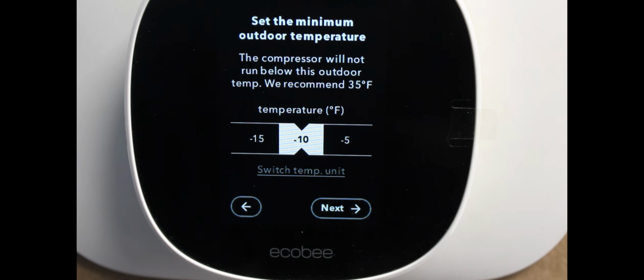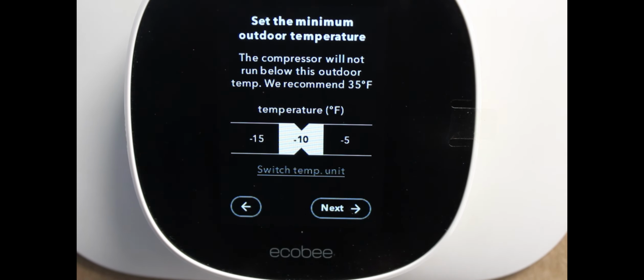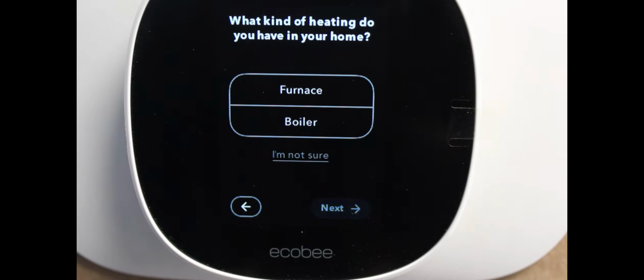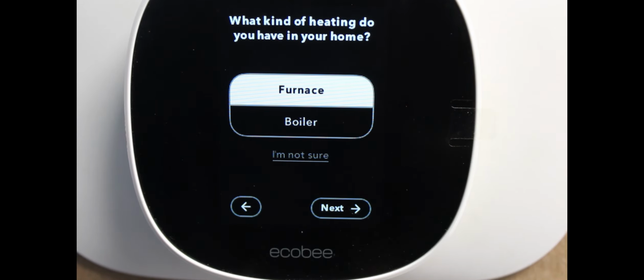If you needed to, you can actually even disable it or have it automatically choose. We're going to set it to -10. That's, you know, most of our modulating units are good down to that temperature, but ultimately it doesn't hurt to at least try to use the heat pump, even if we're down at 0 degrees or so. What kind of heating do you have in your home? It's going to be furnace. If you've got a boiler, obviously select that.